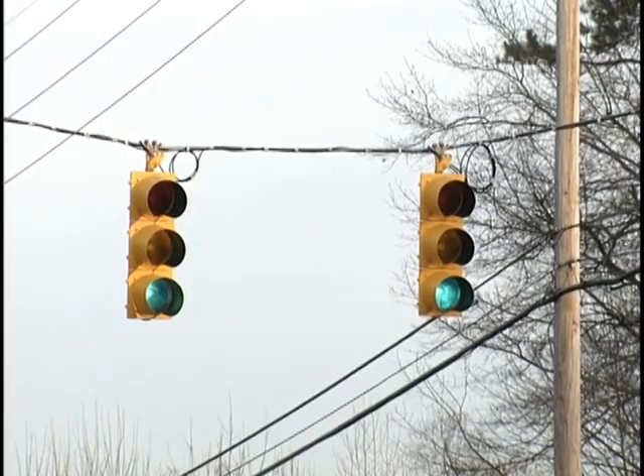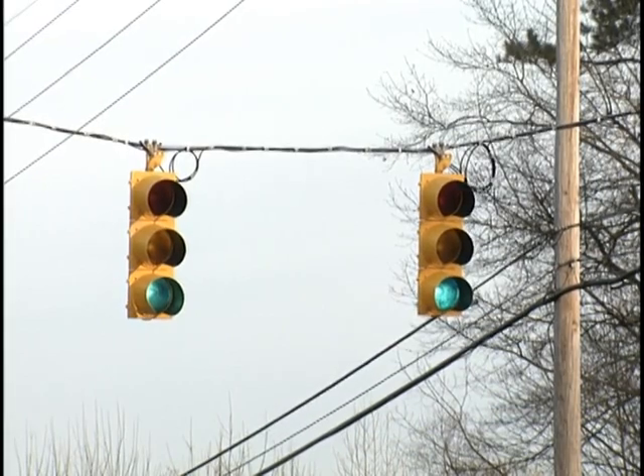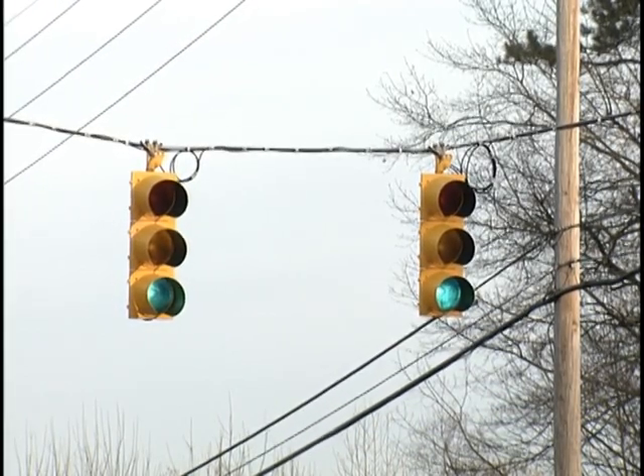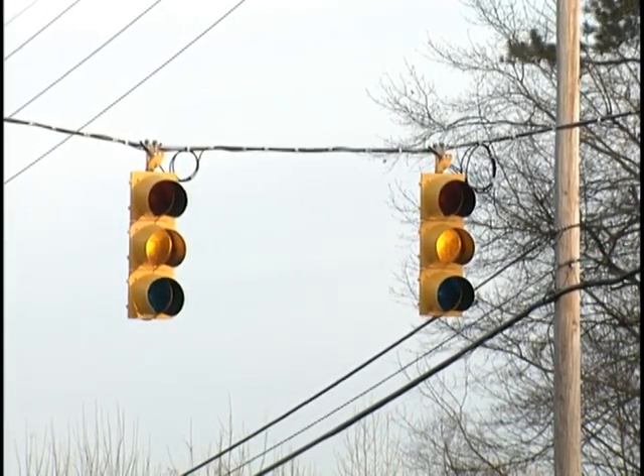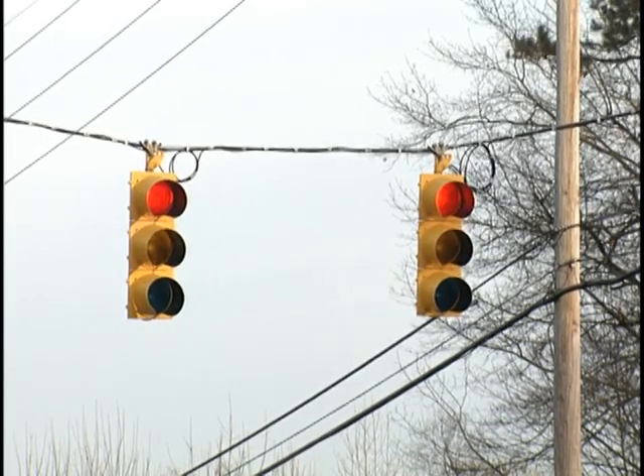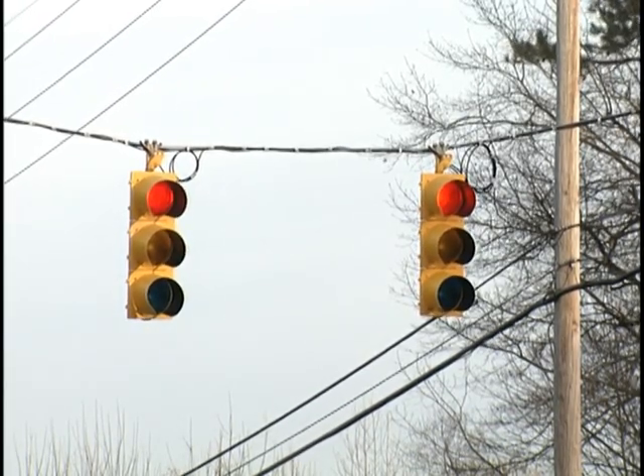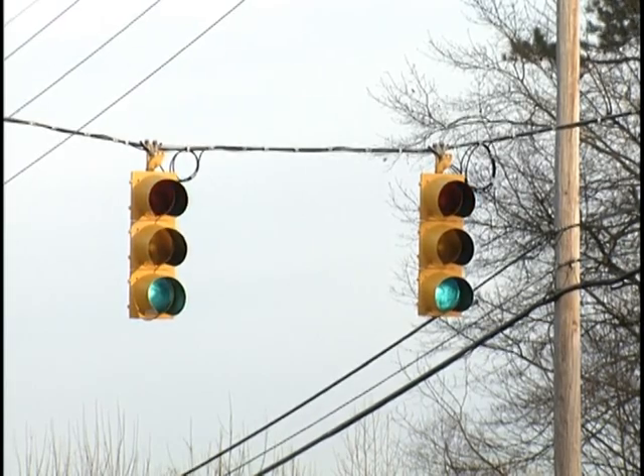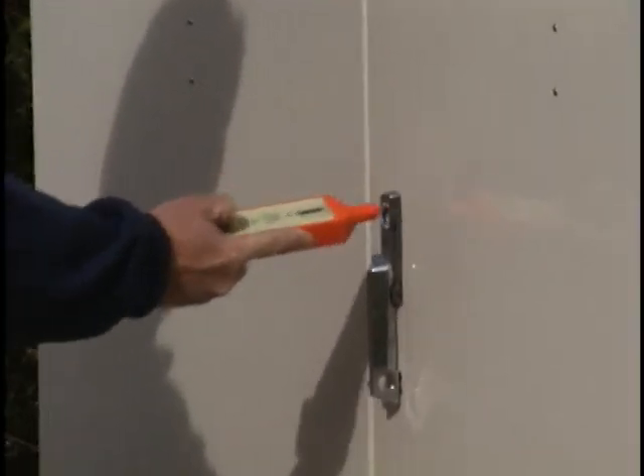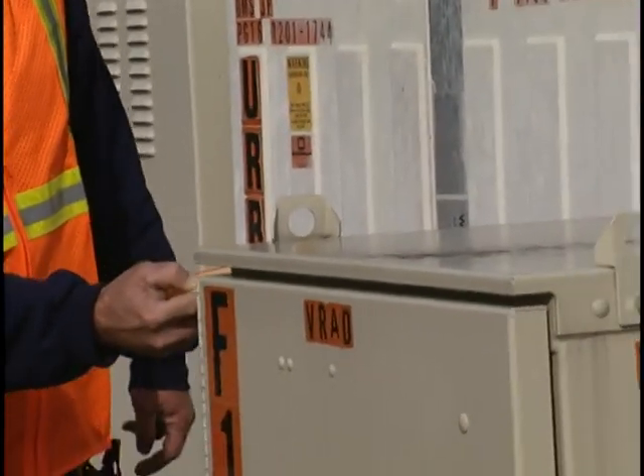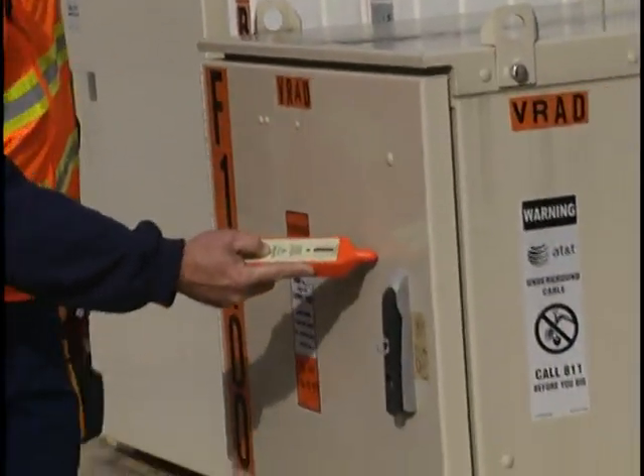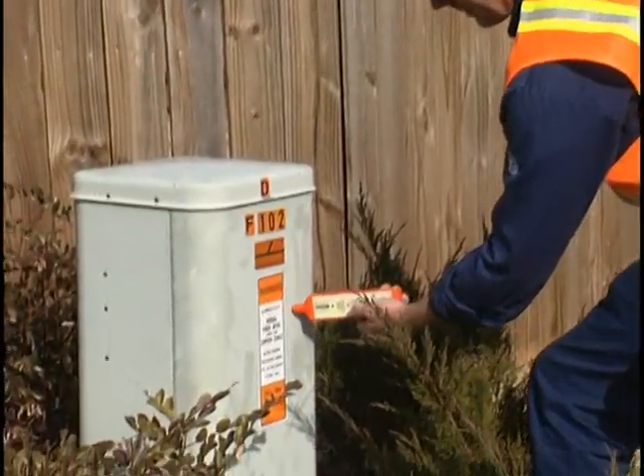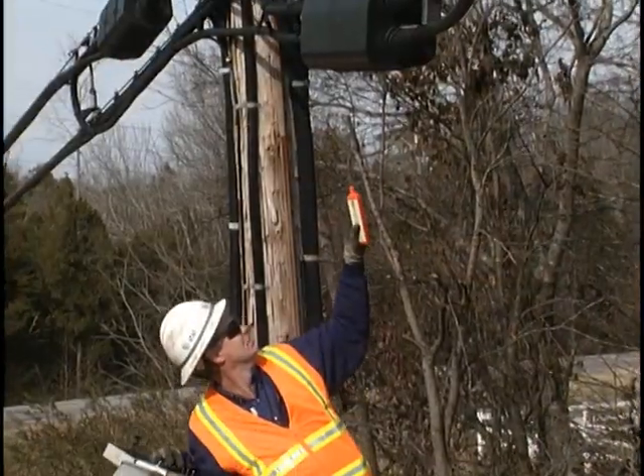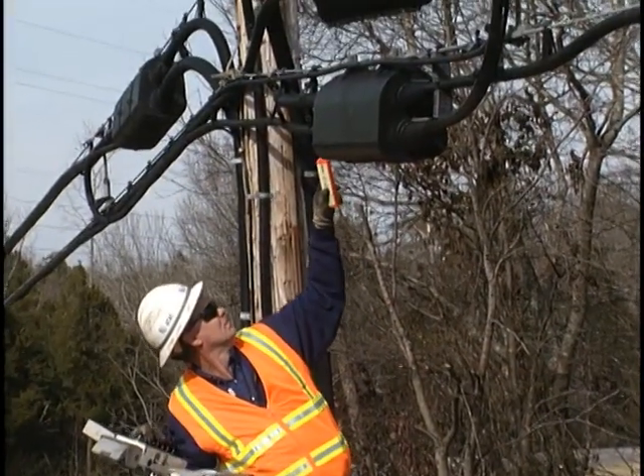When testing a device that is cyclic in nature, such as a traffic light support strand, the technician should always test through at least one complete cycle. This will avoid missing detection of a fault that may occur on a single phase of the cycle. The FVD should be used in any situation where a conductor or object could be energized. Here are some situations where the FVD should be used in our industry, but these are not all of the situations.